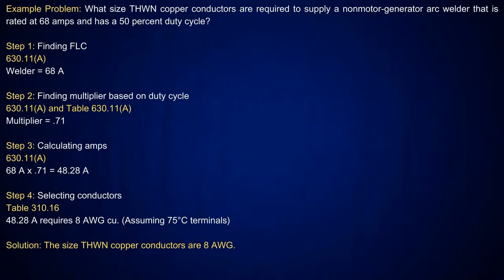Now, when you get to looking at the duty cycle for a non-motor, you're going to look at table 630.11(A). We already know that the welder is good for 68 amps. We gave you the information. Then I go look at the multiplier that's based on the duty cycle in table 630.11(A). It's going to tell you it's 71%. Okay. And the 71% is based on it being a 50% duty cycle. Then all I'm going to do is calculate the 68 amps times 0.71, and that's going to give you 48.28 amps. Go to table 310.16, 75 degrees C column. The next size above that is 50 amps, which requires a number 8 conductor.